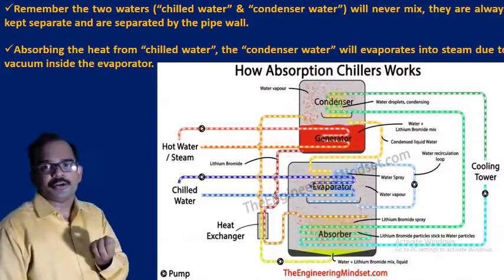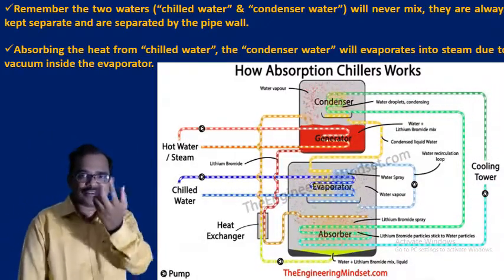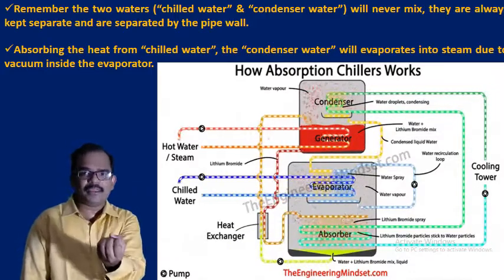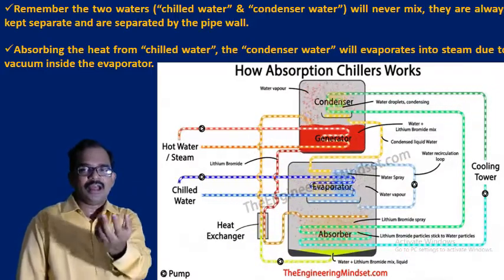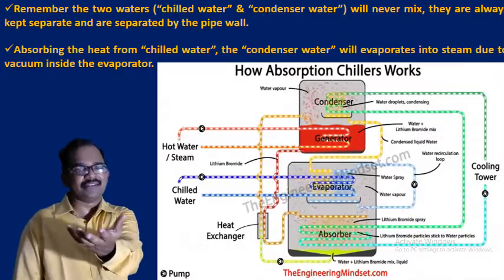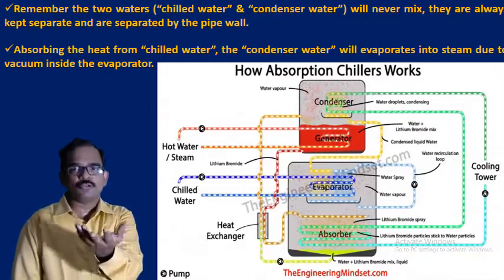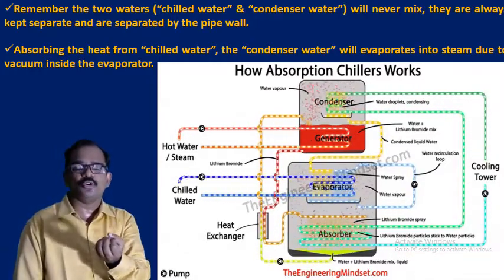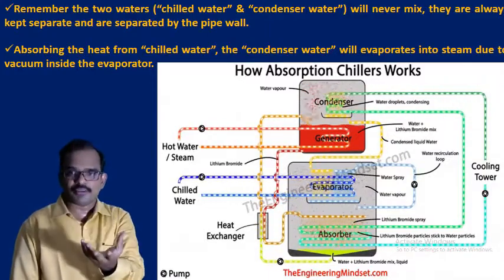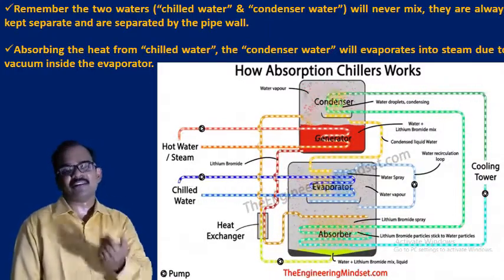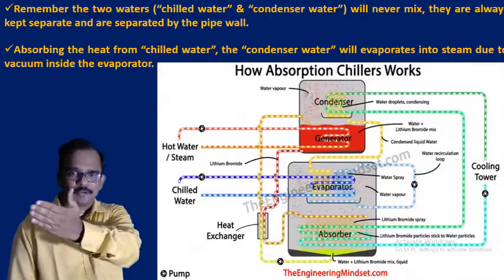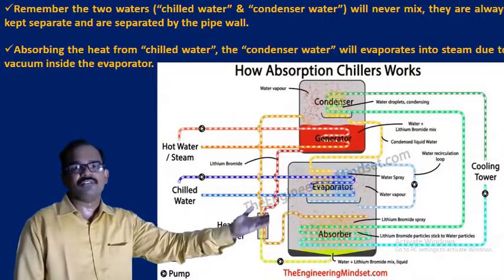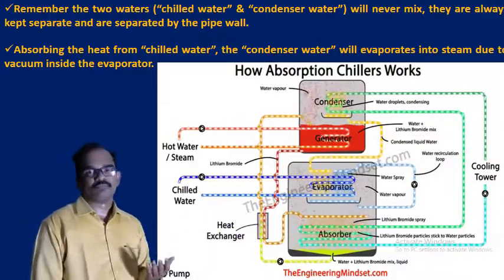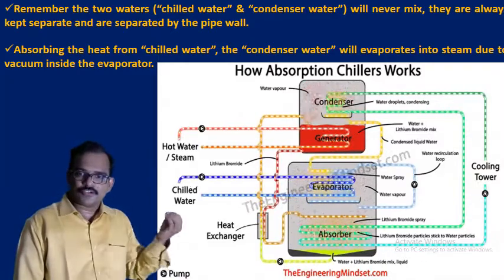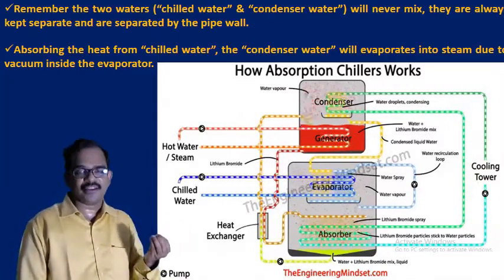What I told you? Now the boiling point of the water in the evaporator will be 4 degrees centigrade. Now I am giving 12 degrees centigrade heat. That is, 4 degrees itself is enough to convert that condensed water into steam or water vapor. That is what is happening here. And the remaining 8 degrees centigrade chilled water will move outward of the evaporator. Is that clear? The chilled water will enter at 12 degrees centigrade.